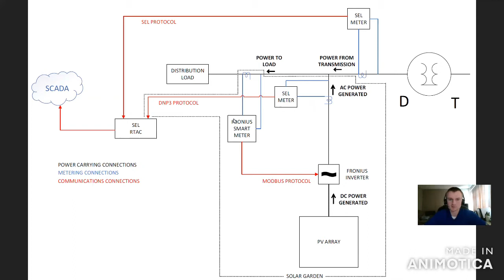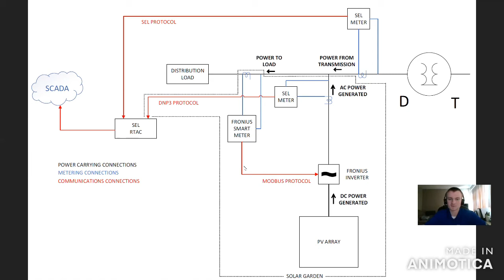We ensure power is not over-injected by tracking how much power is being demanded by the distribution load at all times through this Fronius smart meter, then sending that information to our inverter as the maximum power set point, so we're not injecting more power than the load is demanding.